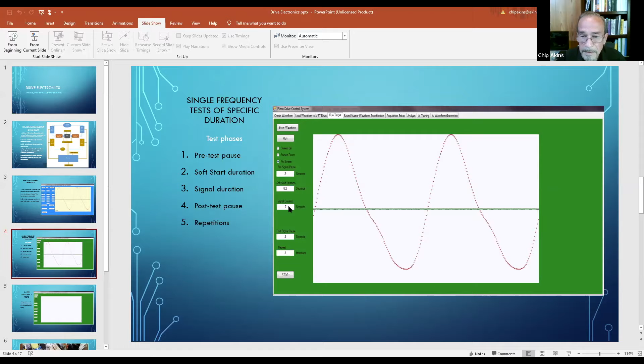We do have the option of running it in sweep mode. In sweep mode, you can specify all the same things as in steady state mode, plus the sweep duration in seconds and the sweep range in kilohertz or hertz. That gives you a lot of precision in finding the fundamental and the harmonics, helping you know exactly what the operating frequency of the device under test is.